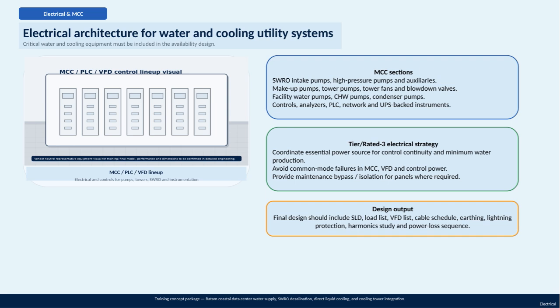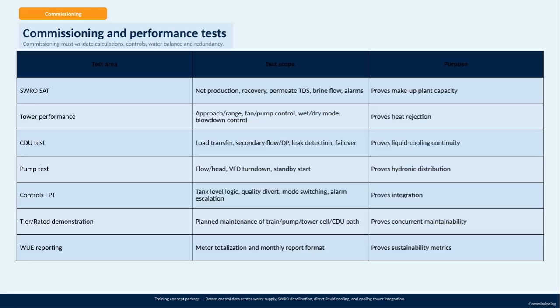Our Tier 3 electrical strategy is designed to maintain control continuity and stable water production by coordinating essential power sources, preventing common mode failures in MCC, VFD, and control power systems, and providing maintenance bypasses or isolation options where necessary. Finally, the design output should be thorough and detailed, including a single-line diagram, load lists, VFD lists, cable schedules, earthing plans, lightning protection, harmonic studies, and a power-loss sequence. This comprehensive documentation ensures the system is robust, maintainable, and ready for any operational challenges. Now, let's discuss commissioning and performance tests, which are crucial for ensuring the system meets its design and operational goals.